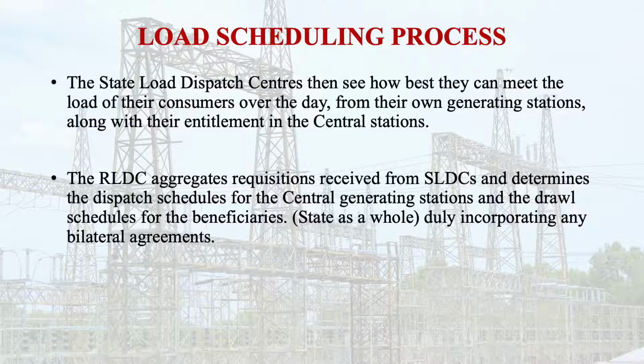Whatever they want from the regional load dispatch center and from the grid, they inform the regional load dispatch centers. So the power draw from the central stations is limited to the entitlement of the day. Every day they have to send their demand, and every day the scheduling is done.